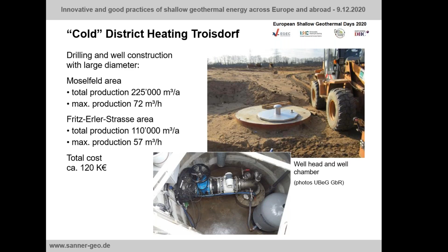During the startup phase, the pumping capacity was a bit too high, so the system wasn't very efficient at the beginning because the pump had to run at the lowest possible stage. Still, for 2 or 3 houses it was too much, but you have to supply that to the houses. That changed quickly once construction of the buildings continued, and it showed nicely that this is a scalable technology. You can add more later on.